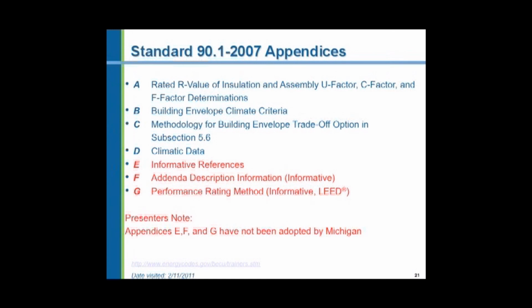Now, Appendix G is used for the LEED performance rating method. It is a voluntary system that is not mandatory. It's not required by law. But if you choose to design your building and apply for LEED credits, then you will be using Appendix G. Appendix A is a very large appendix with a whole bunch of wall, ceiling and roof combinations of elements that have been pre-calculated and U values calculated for them.